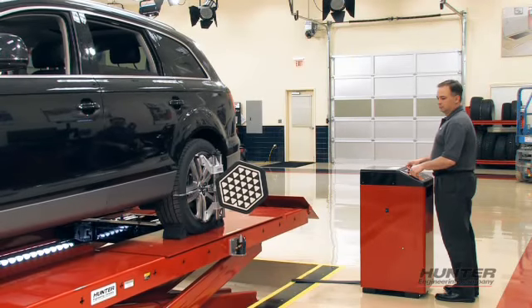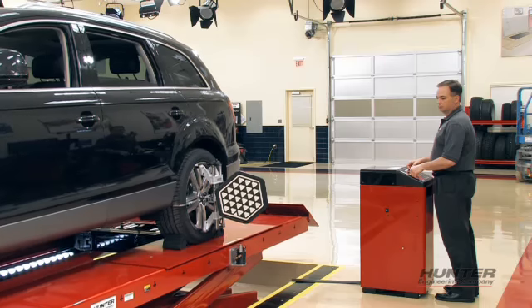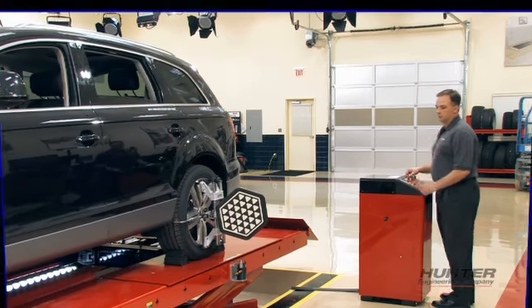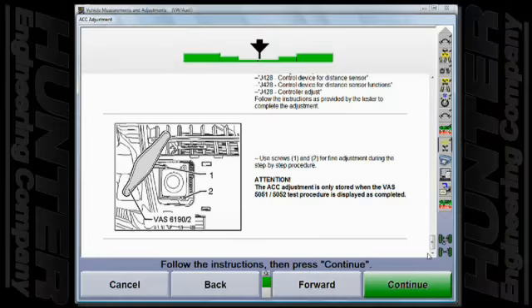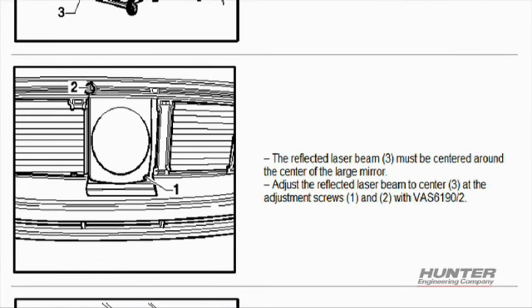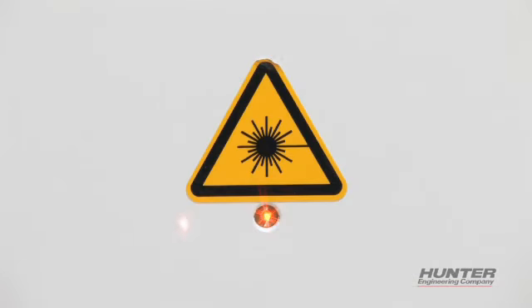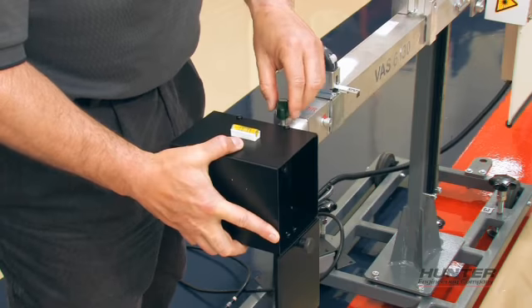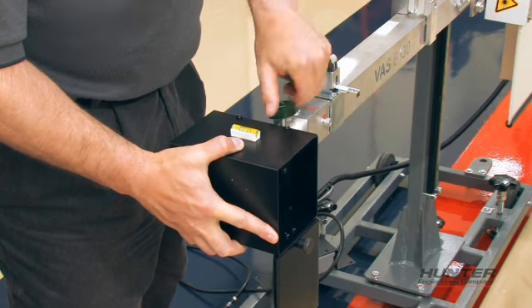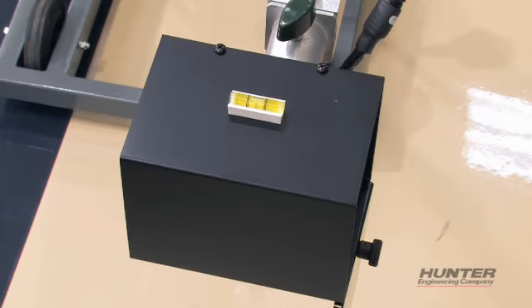If necessary, adjust the height of the rack to achieve proper vertical alignment with the laser beam. When using the mirror adjustment case, center the laser beam vertically on the mirror. Next, adjust the designated screws at the sensor assembly so the reflected laser beam is centered in the emitter opening at the large mirror assembly on the calibration fixture. Recheck and level and lock the aiming cameras on each side of the bar.